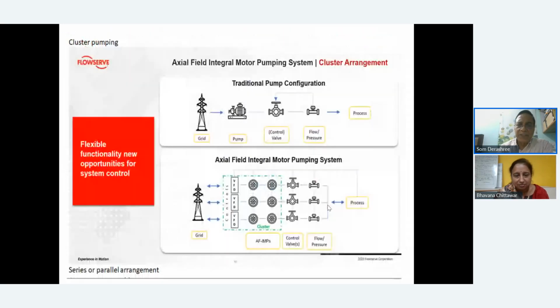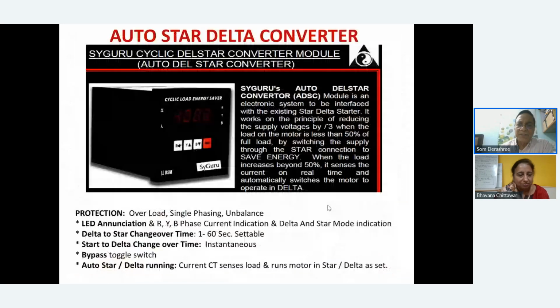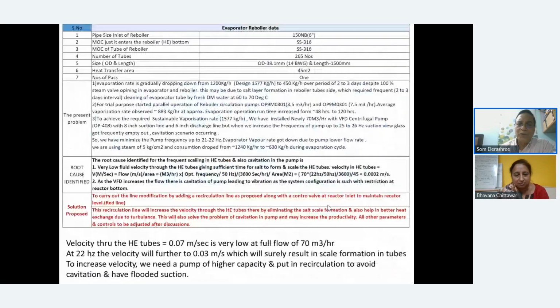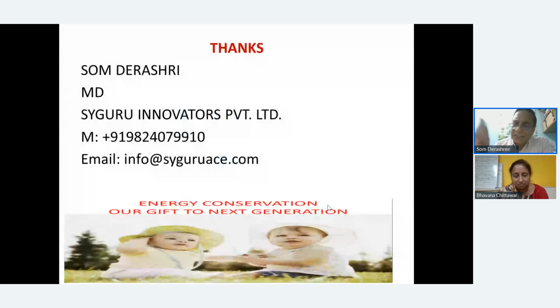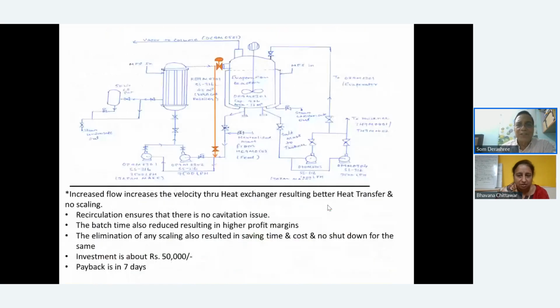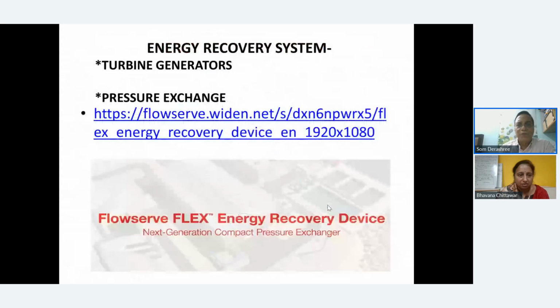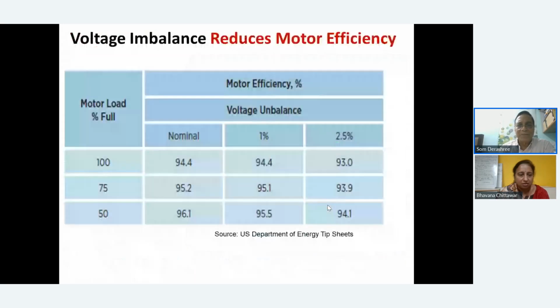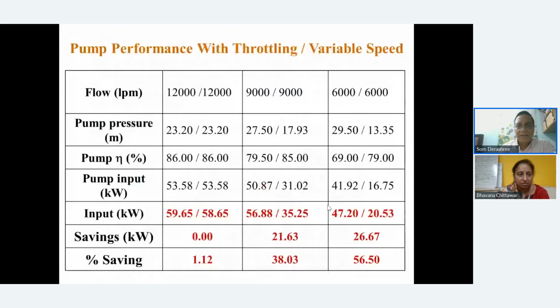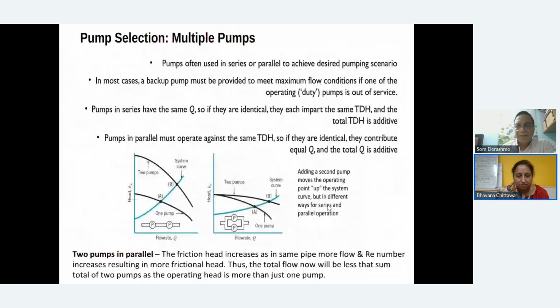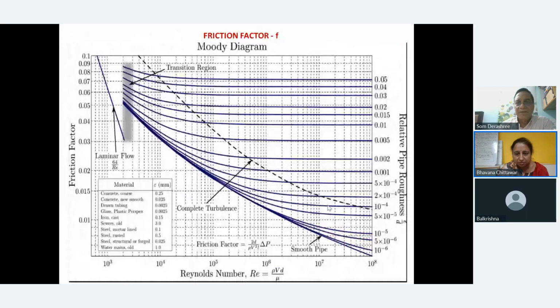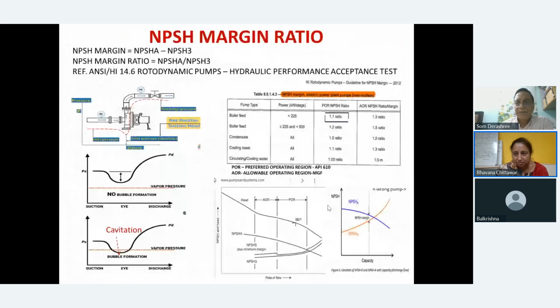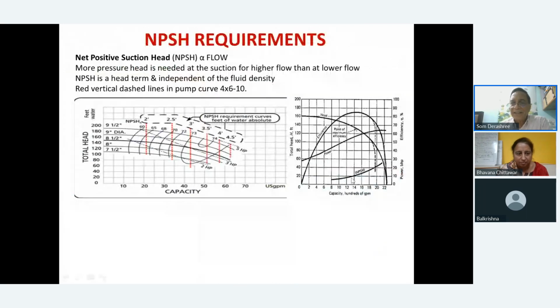And your next question is, when you put a VFD, what happens is the VFD is put to reduce the flow. You don't go beyond 50 hertz, right? It is always less than 50 hertz. So your RPM will reduce, and as I said, flow will reduce. And as the flow reduces, your NPSH required is also reduced. You get my point? I've shown you one curve, no? NPSH required is proportional to the flow. As flow increases, NPSH increases. You see, as the flow is increasing, NPSH is increasing.